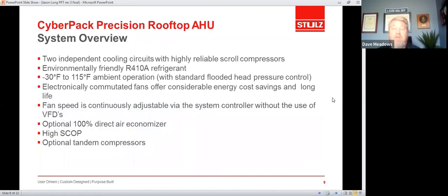The Cyberpack units are designed specifically to operate in both cold and hot ambient environments. If you look at our range there, we're able to operate from minus 30 degrees Fahrenheit up to 115 degrees Fahrenheit with no loss of capacity. We are able to achieve that minus 30 head pressure control utilizing a standard flooded head pressure control system. In other words, at very, very cold temperatures, we backflood the condenser coil with liquid refrigerant to limit its effectiveness. We also have electronically commutated fans, which are extremely energy efficient and lend themselves nicely to very precise control of the airflow rate.